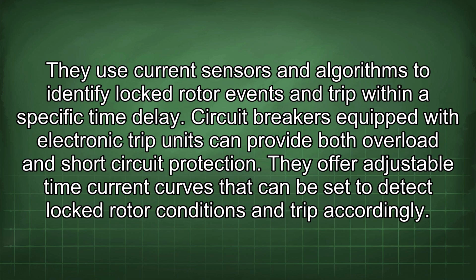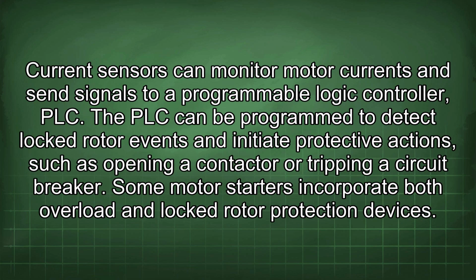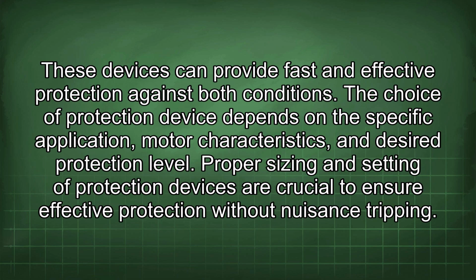Circuit breakers equipped with electronic trip units can provide both overload and short-circuit protection. They offer adjustable time current curves that can be set to detect locked rotor conditions and trip accordingly. Current sensors can monitor motor currents and send signals to a programmable logic controller (PLC). The PLC can be programmed to detect locked rotor events and initiate protective actions, such as opening a contactor or tripping a circuit breaker. Some motor starters incorporate both overload and locked rotor protection devices. These devices can provide fast and effective protection against both conditions.